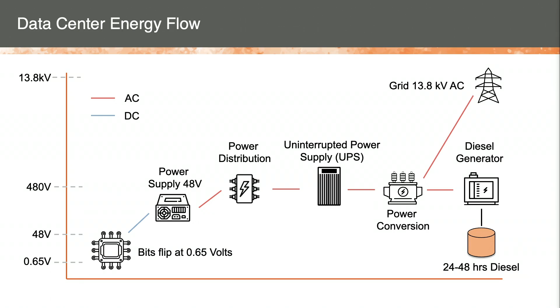Now we're looking at 200 gensets, and these are not the small ones you can buy at Home Depot or Lowe's. These are large containerized machines, and if all 200 of them kick on at the same time, that is a lot of power. The efficiency of a diesel genset is around 40%, but the amount of fuel storage you need can be as much as 165,000 gallons of fuel. The other challenge you have here is that backup system, which is a lot of infrastructure, sits all the way on the right. And by the way, that backup system is similar to powering a small city, maybe even a medium-sized city. That is a pretty darn good power plant.